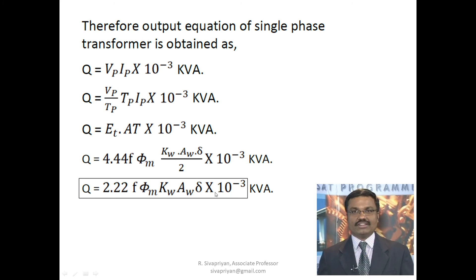This output equation Q = 2.22×f×φm×Kw×Aw×δ×10⁻³ kVA is the same for both single-phase core type and single-phase shell type transformers. Here φm is the maximum value of flux in the core. Instead of φm, we can also use Bm×Ai, where Bm is the flux density and Ai is the net iron area. This gives the generalized output equation for single-phase transformers.